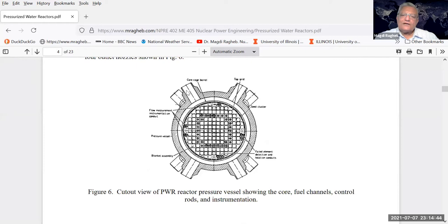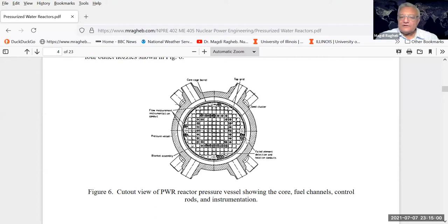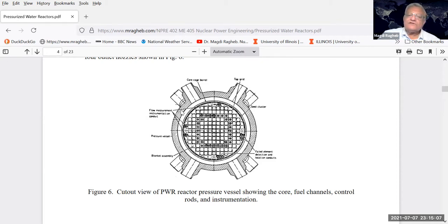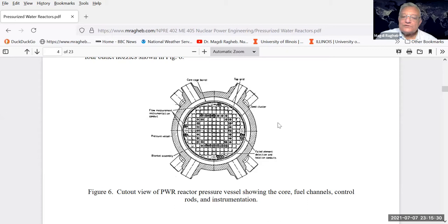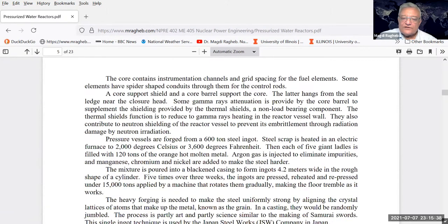Looking at the core from the top, you find the pressure vessel, very thick. Radiation from the center of the core, particularly neutrons, can embrittle the steel. So we provide another vessel called the thermal shield, which shields the outside steel vessel from the effect of neutrons and thermal radiation. You have channels in which the coolant will flow. Each cross here represents a control rod coming into the core, and there are also channels for instrumentation to measure power level, flow rate, temperature, and pressurization.